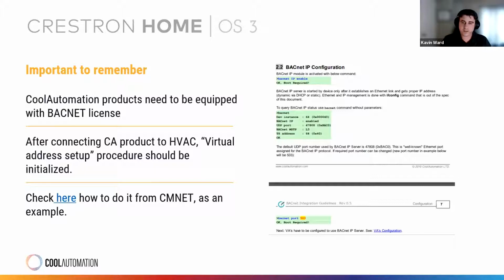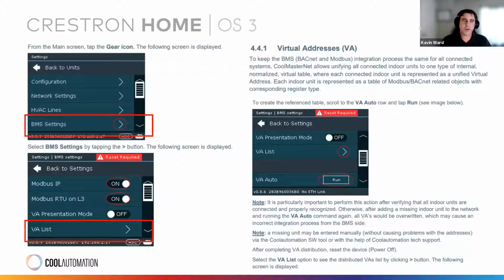We do have the ability to set your device instance number and the address, and we're happy to support you with that if it needs to be changed. After confirming that the BACnet license is enabled and the units are actually discovered on the device, we need to run the virtual address setup. We have instructions on how to complete that as well. It can be done directly from the CoolMasterNet. Simply go to the settings, BMS settings, VA list, and run VA auto. And this will assign a virtual address to each of the connected indoor units, allowing it to communicate via BACnet so that it can be discovered.